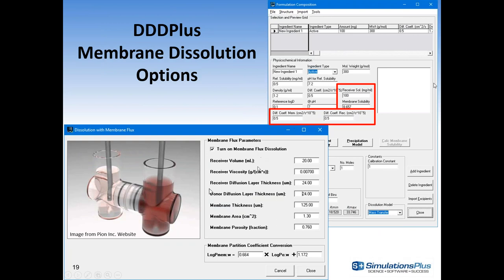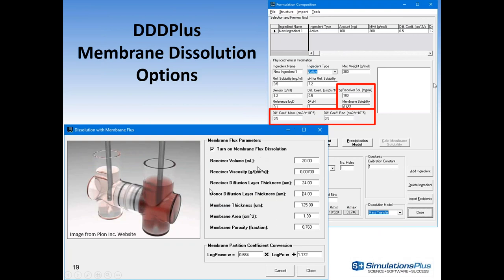All inputs are available: receiver volume, viscosity of the receiver fluid, diffusion layer thicknesses, membrane thickness, membrane area, and membrane porosity. We assume the membrane is filled with a phospholipid-type material, using a correlation that relates log P in octanol/water to the membrane partition coefficient. The receiver solubility can be entered manually, as different companies may use different proprietary fluids. You can also set the diffusion coefficients.